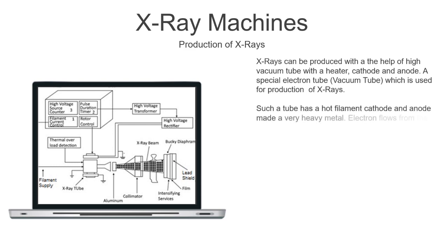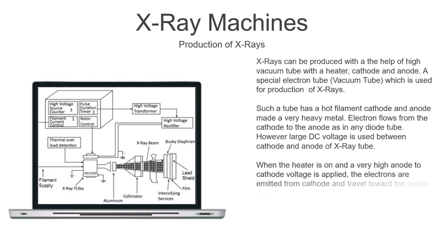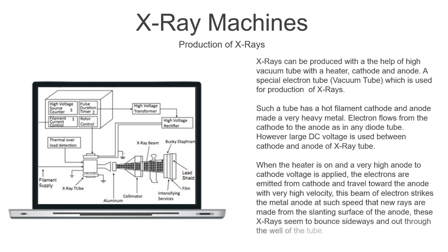So now let's talk about the production of X-rays. X-rays can be produced with the help of a high vacuum tube, a heater, cathode and anode. A special electron tube — that is, a vacuum tube — is used for the production of X-rays. Such a tube has a hot filament cathode and an anode made of very heavy metal. Electrons flow from the cathode to the anode as in any diode tube. However, a large DC voltage is used between cathode and anode. When the heater is on and a very high anode-to-cathode voltage is applied, electrons are emitted from the cathode and travel towards the anode with very high velocity. This beam of electrons strikes the metal anode at such speed that new rays are made from the slanting surface of the anode. These X-rays seem to bounce sideways and out throughout the wall of the tube.